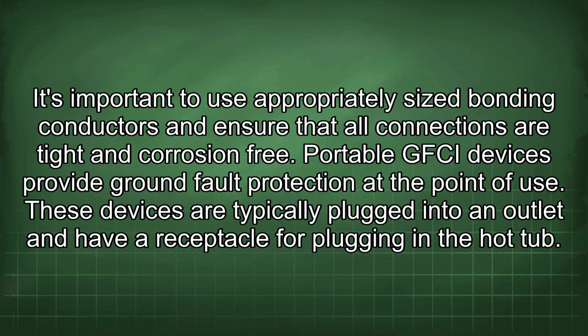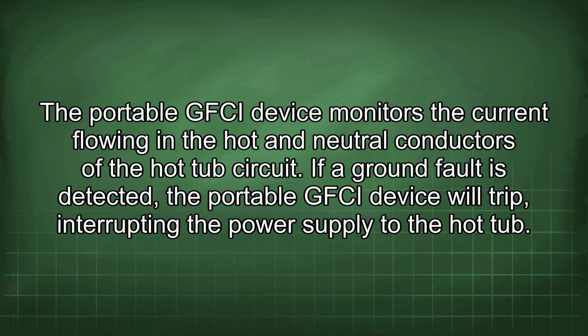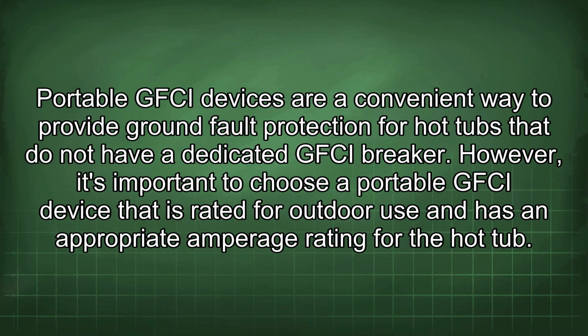Portable GFCI devices provide ground fault protection at the point of use. These devices are typically plugged into an outlet and have a receptacle for plugging in the hot tub. The portable GFCI device monitors the current flowing in the hot and neutral conductors of the hot tub circuit. If a ground fault is detected, the portable GFCI device will trip, interrupting the power supply to the hot tub. Portable GFCI devices are a convenient way to provide ground fault protection for hot tubs that do not have a dedicated GFCI breaker. However, it's important to choose a portable GFCI device that is rated for outdoor use and has an appropriate amperage rating for the hot tub.